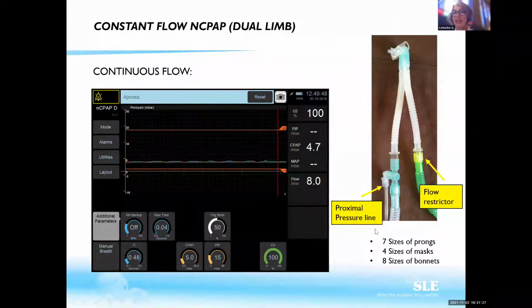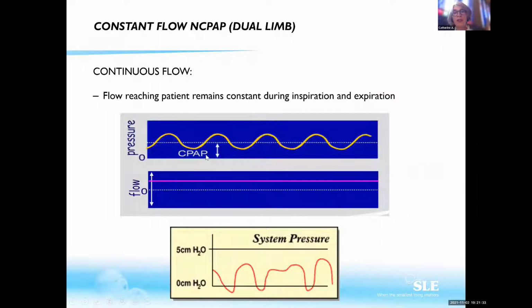This is a type of CPAP where you will have two limbs on your CPAP. What you set here is a CPAP of, for example, 5. If you set a CPAP of 5, the ventilator will be pushing something like 8 liters per minute to generate a CPAP of 5. So during the inspiration, the patient will receive 8 liters per minute, whatever the breath he's taking. Small breath, deep breath, doesn't matter. He will receive continuously 8 liters to generate the 5 millibar of pressure. When the patient exhales, he will be exhaling against 8 liters per minute.